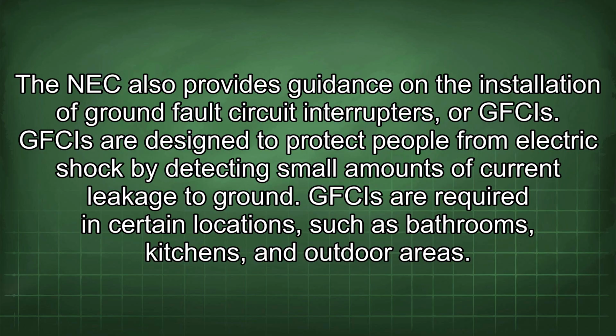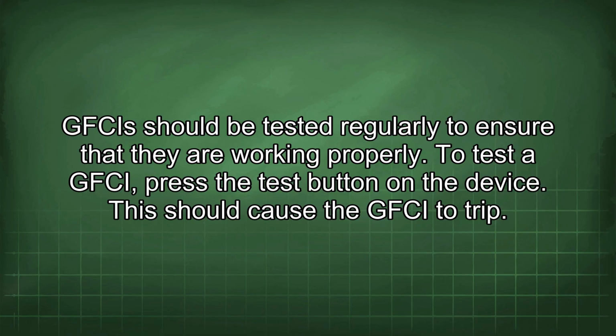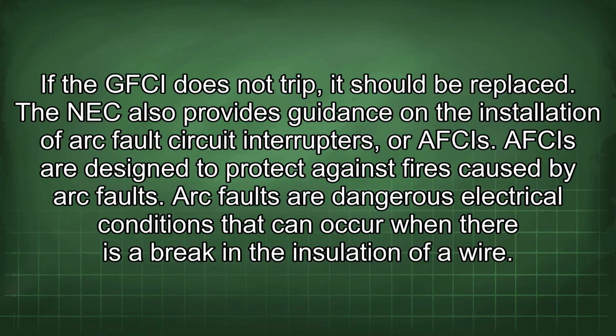The NEC also provides guidance on the installation of ground fault circuit interrupters, or GFCIs. GFCIs are designed to protect people from electric shock by detecting small amounts of current leakage to ground. GFCIs are required in certain locations, such as bathrooms, kitchens, and outdoor areas. GFCIs should be tested regularly to ensure that they are working properly. To test a GFCI, press the test button on the device. This should cause the GFCI to trip. If the GFCI does not trip, it should be replaced.